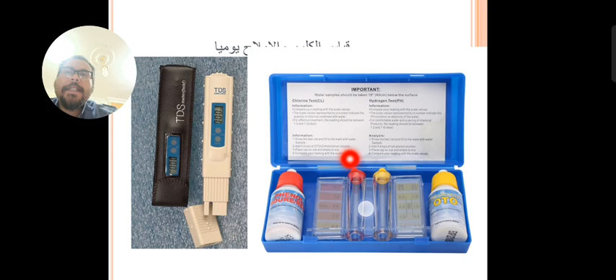Also, we test the chlorine every shift because chlorine is very harmful for the patient if present in the water. This test is done with a sample of water, then we add 4 drops of this reagent. If the water turns yellow, this means there is chlorine in the water, and the dialysis must be stopped and not completed. Every shift we must check these two tests, chlorine and TDS. This yellow color means there is chlorine in this sample and the hemodialysis must be stopped.